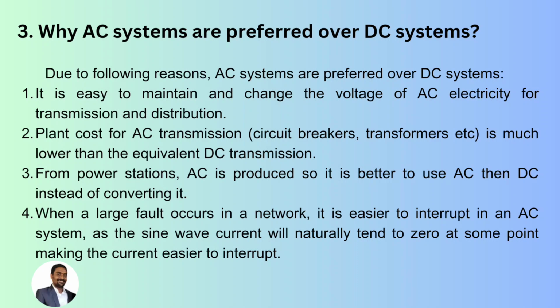Why are AC systems preferred over DC systems? Due to the following reasons, AC systems are preferred over DC systems. It is easy to maintain and change the voltage of AC electricity for transmission and distribution. Plant cost for AC transmission, circuit breakers, transformers, etc., is much lower than the equivalent DC transmission. From power stations, AC is produced, so it is better to use AC than to convert it to DC. When a large fault occurs in a network, it is easier to interrupt in an AC system, as the sine wave current will naturally tend to zero at some point, making the current easier to interrupt.